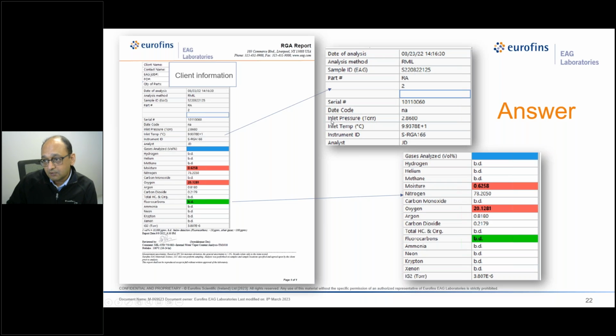This is a question that we often get: what is this inlet pressure? So going back to the individual component where I defined, the sample chamber has this Baratron pressure gauge, which is measuring the pressure in the sample chamber when we puncture the sample or when we introduce the calibration gas. So that is the pressure read in the sample chamber just after the background check, 5 scans, and just after the sample is introduced into the system.